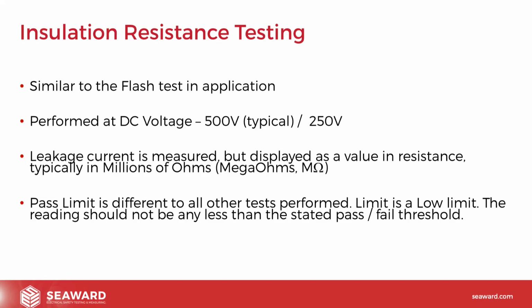What happens internally within the device is it takes the output voltage, takes the known leakage current that's flowing back into the device, and then converts the reading into a resistance reading. Now, what's important to note is when you do perform an insulation resistance test, the reading you're getting is different to any other test that you perform in the electrical safety environment, whereby the limit we normally read is what we call a ceiling level limit. So we want to be beneath the ceiling. In the instance of the insulation resistance, what we're looking for is a floor limit reading. So our pass-fail threshold, we need to be above that.